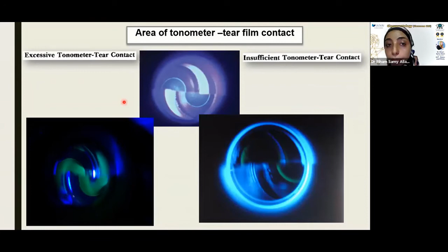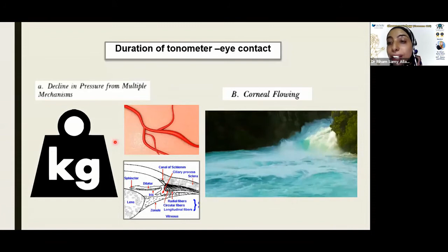Another source is the duration of tonometer to eye contact. When you put the applanation over the eye, you should not exceed half a minute in your measurement, because if the pressure of the applanation is still exerted on the cornea, we have a decline of the intraocular pressure, or an underestimation of the pressure, probably due to the mechanical effect of the probe itself, sometimes due to vascular causes, which is seen in tense patients, or due to accommodation exerted by the patient if he looks just at the applanation. We usually instruct the patient to look away in order to avoid this. Another thing is related to the corneal viscoelastic material, which is known as corneal flowing. With prolonged contact of the applanation to the cornea, it yields, and thus underestimation occurs.